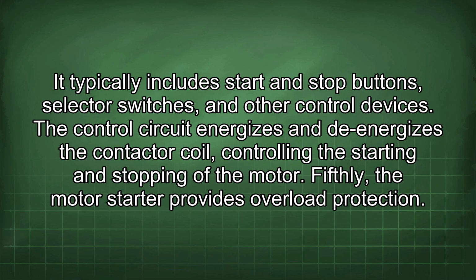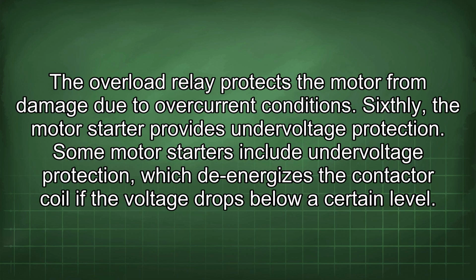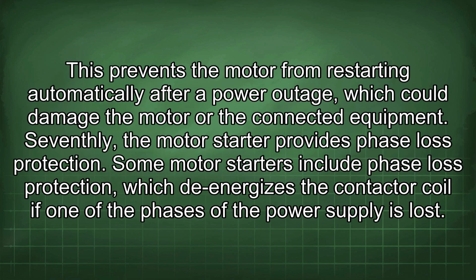Fifthly, the motor starter provides overload protection. The overload relay protects the motor from damage due to overcurrent conditions. Sixthly, the motor starter provides undervoltage protection. Some motor starters include undervoltage protection, which de-energizes the contactor coil if the voltage drops below a certain level. This prevents the motor from restarting automatically after a power outage, which could damage the motor or the connected equipment.